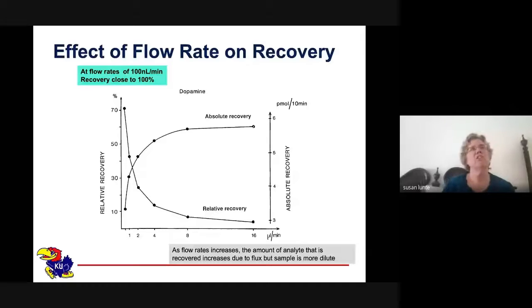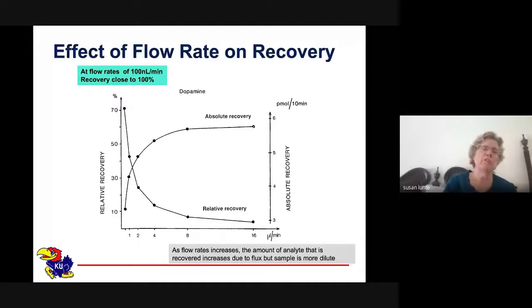So an important thing about microdialysis is, because the sampling is a diffusion-based method, the slower you pump the perfusate through the probe, the more analyte you get into the probe. So if you pump at a slow enough flow rate, you basically reach equilibrium with the extracellular fluid. And so your recovery is close to 100% because the concentration of the analyte in the extracellular fluid is the same as that in the perfusate. So if you go down to flow rates of about 100 nanoliters per minute, your recovery becomes close to 100%.